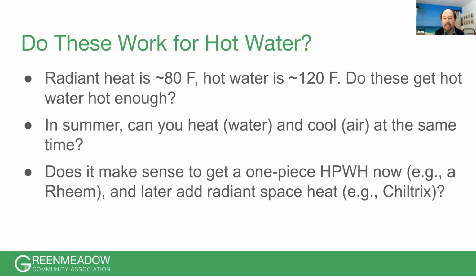Inside the control logic, what has to happen when there is a call for domestic hot water is the heat pump has to go to a higher temperature. So it leaves the hydronic radiant heat temperature and goes to a higher temperature temporarily while there's a hot water demand. That's the key feature that these heat pump manufacturers have to be able to supply in order to do domestic hot water heating. Like with SpacePack and AirMech, and I think the other ones, we have to use a flat plate exchanger and two pumps. With a Chiltrix, it's just the indirect water heater and the pump that's internal to the heat pump under most circumstances, unless there's a great distance between the heat pump and the tank.